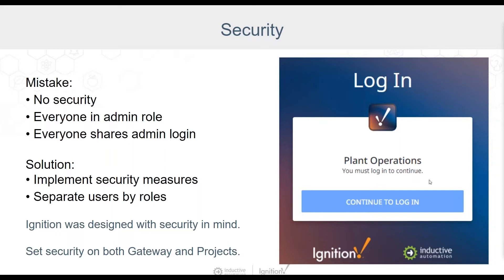It's also important to note that you should not give everyone the admin login or place all users in the default admin role — this is a common mistake. No matter if you are using internal Ignition security or an external provider, you will want to create roles for security. Projects are more open by default; all menus, button clicks, and set points are open as long as any user is logged in.